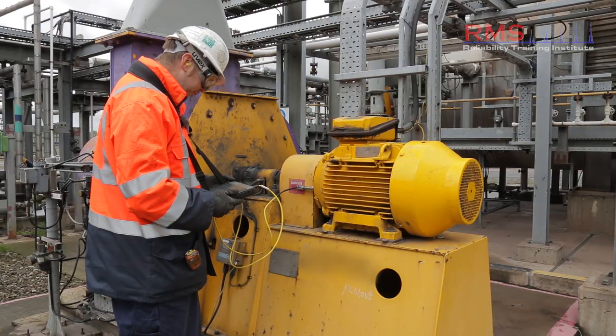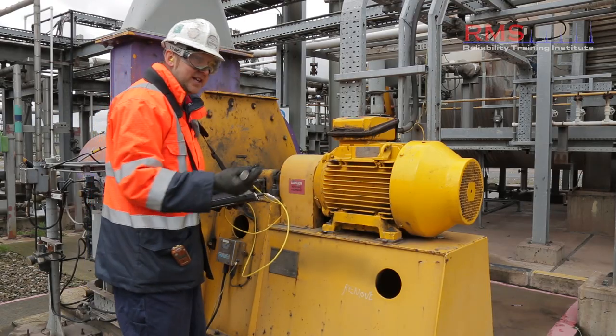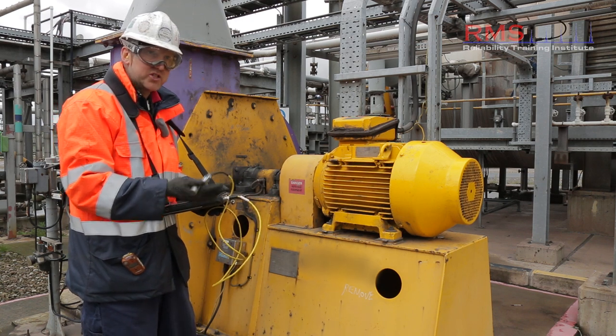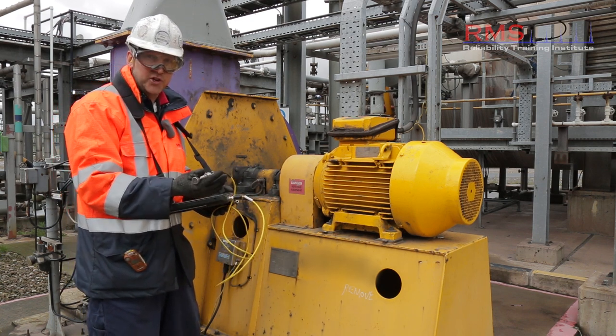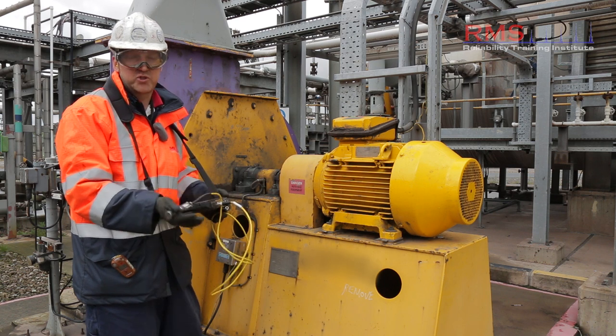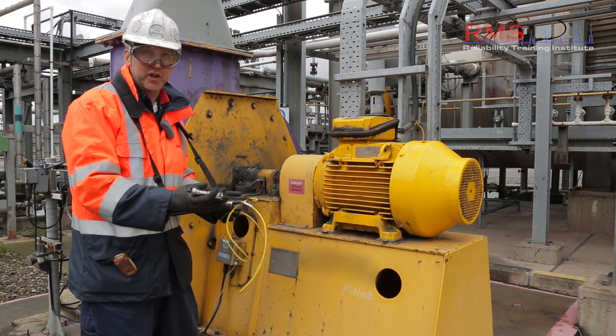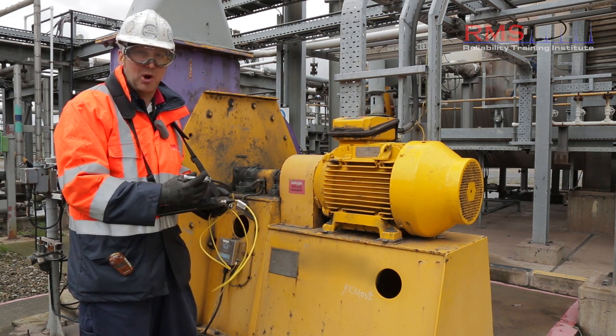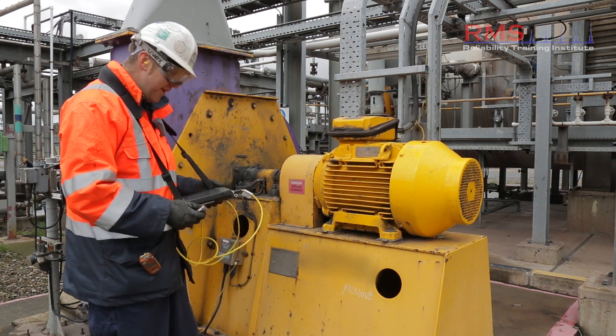That's okay. What I will say on these readings, I'm dual channeling it. So on each bearing, I've got a standard reading and a PeakVue envelope reading, just looking for bearing and impacting problems. So let's go on the fan now.